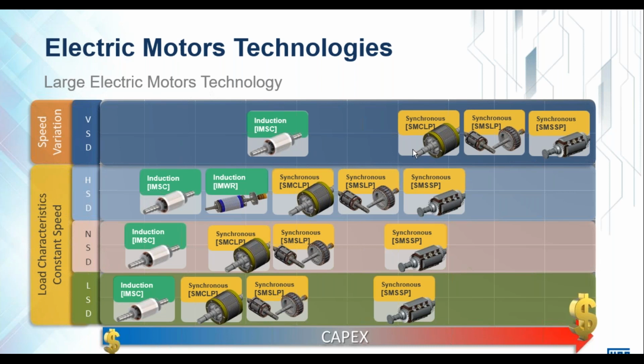Just to chat about this, a synchronous motor on VSD application. In most cases, a synchronous motor would be used where you need to adjust the power factor for reactive power control, where you want to put reactive power back into the system to increase your overall plant power factor. You can use a synchronous machine on a VSD application or with a VSD. However, if it is permanently connected to the VSD, it is the VSD that controls the power factor and no longer the synchronous motor. That power factor would hover close to unity, but would be in the region of 0.97 lagging. So it is not necessarily a practical solution to use a VSD started and operated synchronous motor.